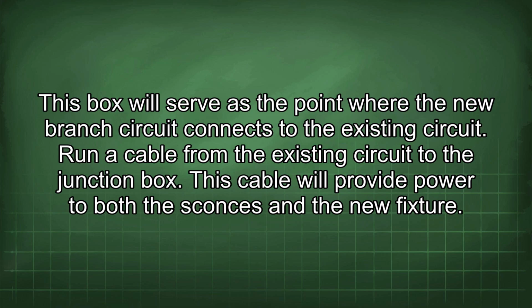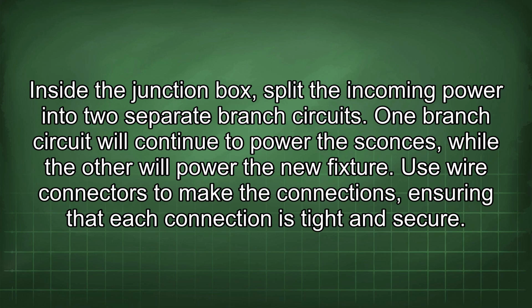Run a cable from the existing circuit to the junction box. This cable will provide power to both the sconces and the new fixture. Inside the junction box, split the incoming power into two separate branch circuits. One branch circuit will continue to power the sconces while the other will power the new fixture. Use wire connectors to make the connections, ensuring that each connection is tight and secure.